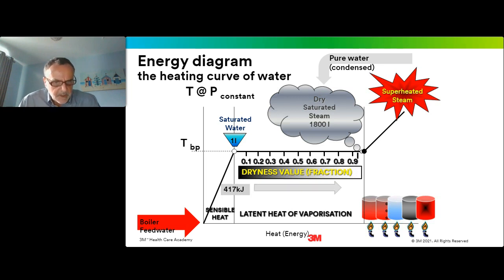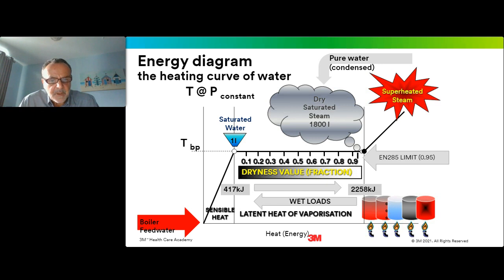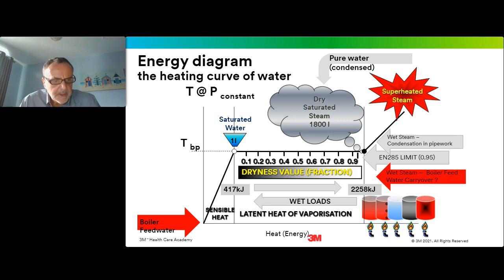So if we consider the points where the water quality has an impact, I'll just quickly click through these. The first is, of course, down in this bottom left-hand corner, the quality of the boiler feed water. Now, some people might use potable water in their boiler, which means that whatever contamination is present in the potable water will end up in the boiler. And if you have small droplets carried over in your steam, then it will also end up in the steam. And this is why some people would either use purified water, either as reverse osmosis, or certainly softened water to avoid furring up the heating elements inside the boiler.